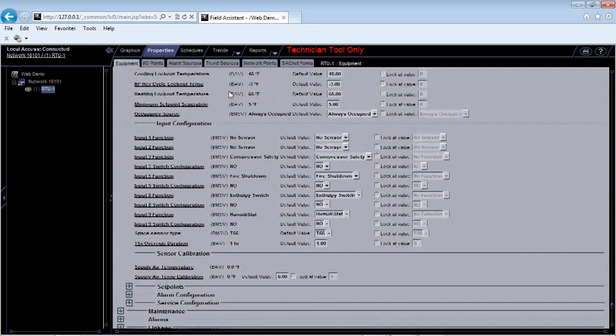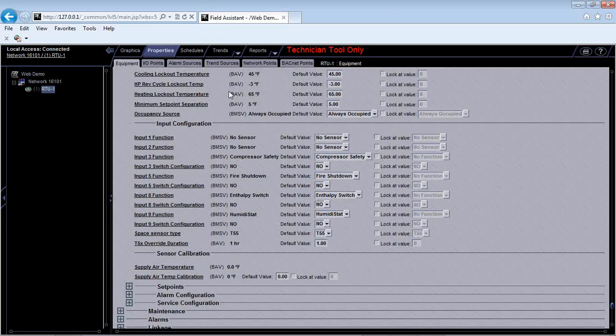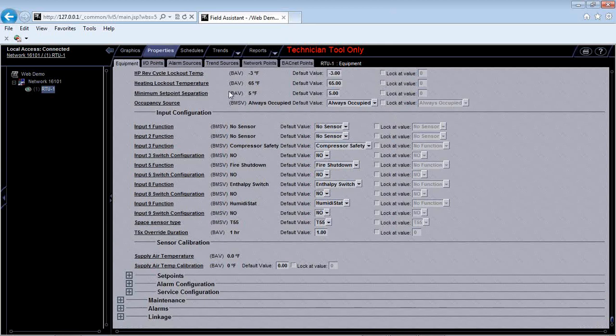Heat pump reverse cycle lockout temperature. I've never installed one of these on a rooftop heat pump. I've never even seen a rooftop heat pump. But that's your delta for locking out your heat pump, your reverse cycle. I've honestly never seen it, but if you want to type that value in, you're more than welcome. It's not going to do anything unless you have a heat pump and reversing valve set up. You also have a heating lockout temperature on here. You can see that defaults to 65 degrees. That is, you don't want to ever allow heat above 65 degrees, only below it.